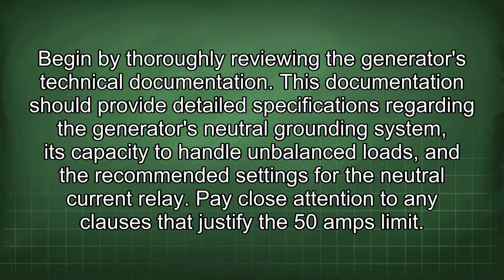This documentation should provide detailed specifications regarding the generator's neutral grounding system, its capacity to handle unbalanced loads, and the recommended settings for the neutral current relay. Pay close attention to any clauses that justify the 50 amps limit.